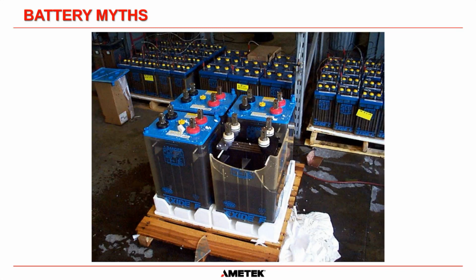And the same if the flame arrestor is broken. What you'll find is, because flame arrestors push and twist in, sometimes the porous stone comes away from the bottom of the flame arrestor, and there's not a true connection anymore because the glue breaks. Once that happens, you must replace that flame arrestor immediately, or hydrogen will escape out and that flame arrestor will not prevent any ignition of gas out here from getting back into the cell. So cracked jars or flame arrestors that don't work are extremely dangerous and should be replaced immediately.